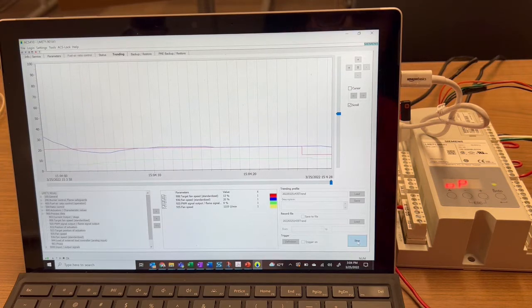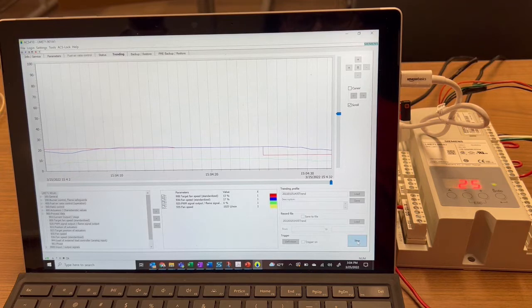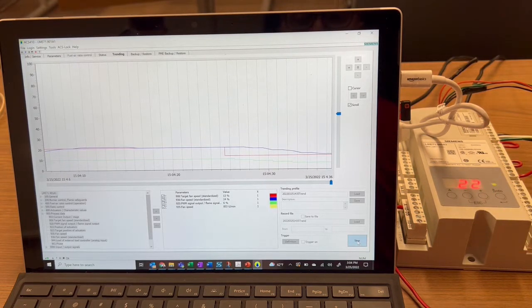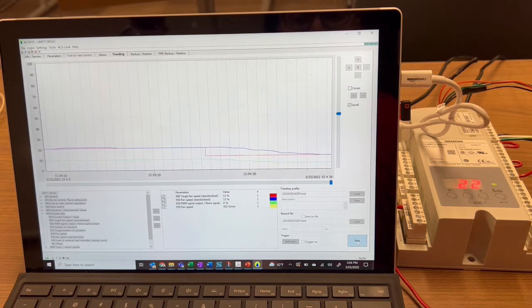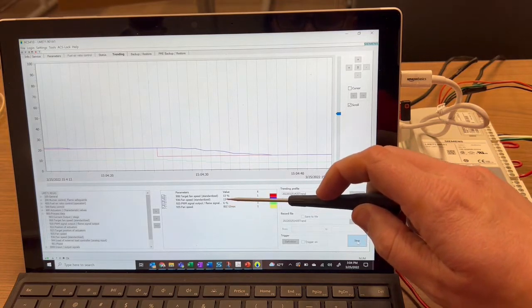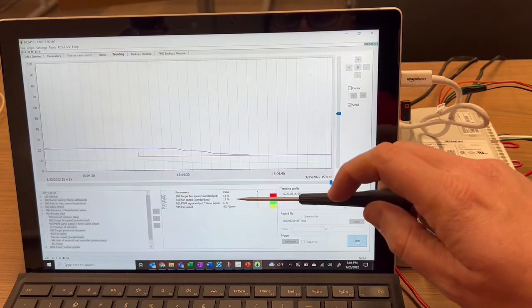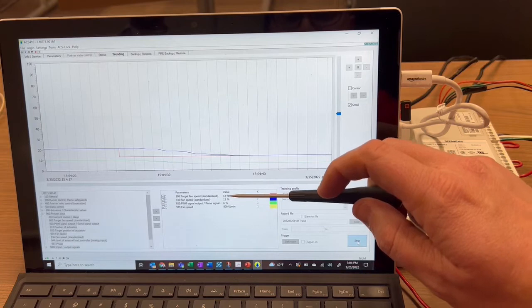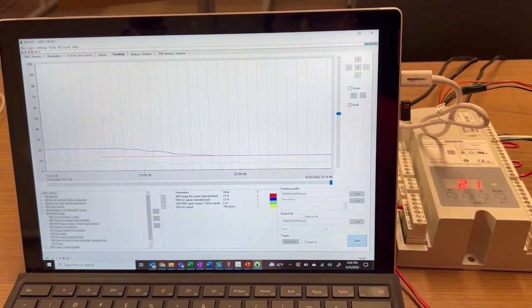We are now in operation and it's now listening to the analog signal. It's driving down to low fire. And we notice that the PWM signal is fairly low. And in this example is 6%. And we see our blower speed and target speed is 13%, all controlling steadily.